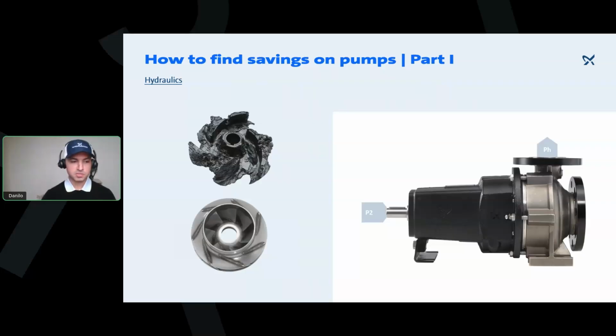I personally have the experience of walking into buildings and seeing pumps from the 80s, from the 90s, and they're still running, right? So here, at least in the United States, what happened was in 2016, that's when the US Department of Energy, the DOE, started issuing the first ever energy conservation standard for certain clean water pumps, right? And then working together with Hydraulic Institute, by 2020, the DOE reviewed the process and updated regulations. From that point on, all manufacturers in the United States had to change certain hydraulic parts to increase the efficiency of their pumps, else they wouldn't be legally allowed in the market. And that's when what we call the PEI came about, right? The Pump Energy Index, Efficiency Index.